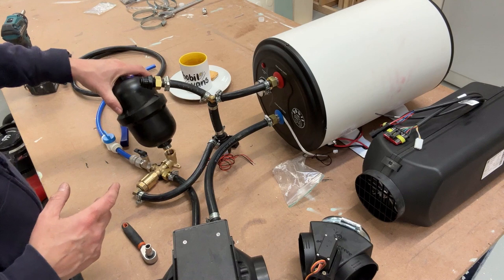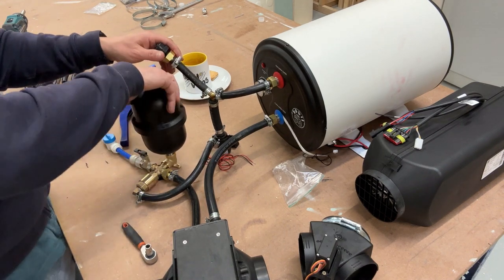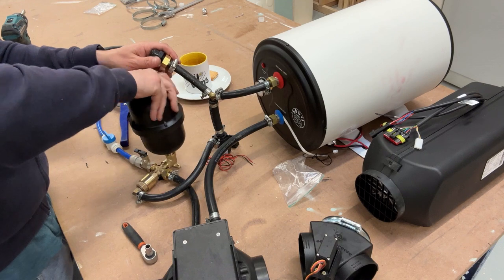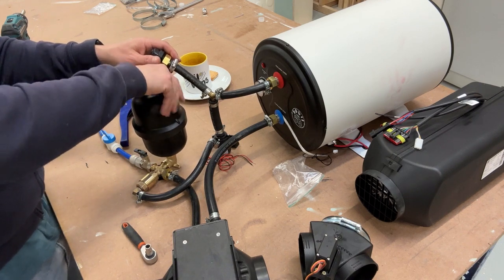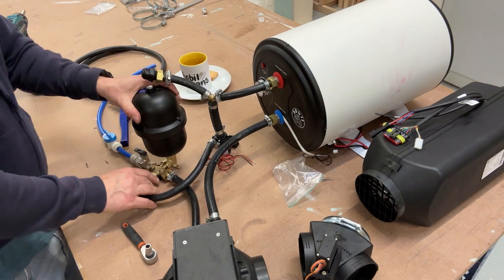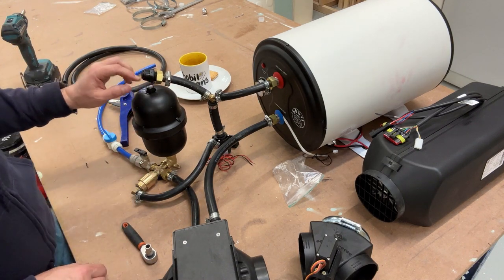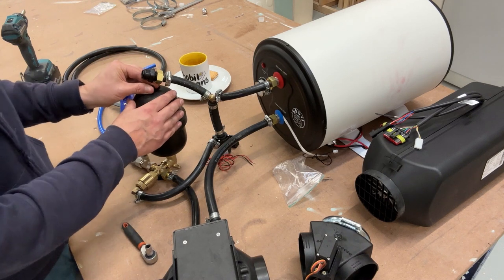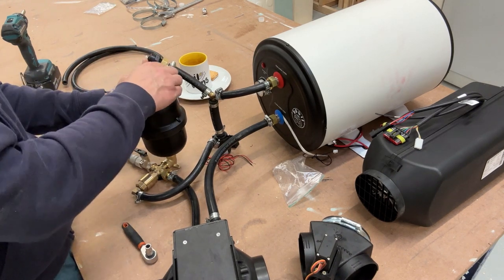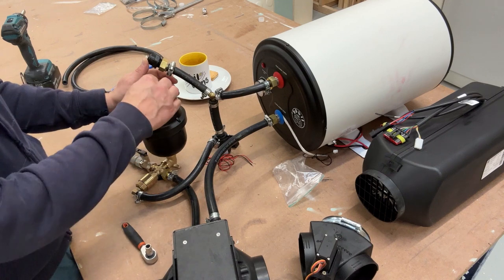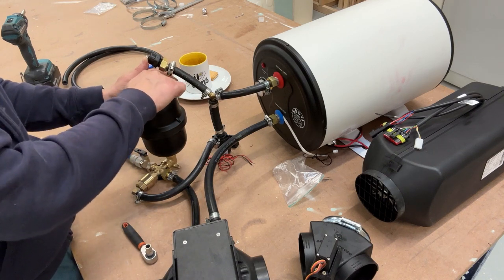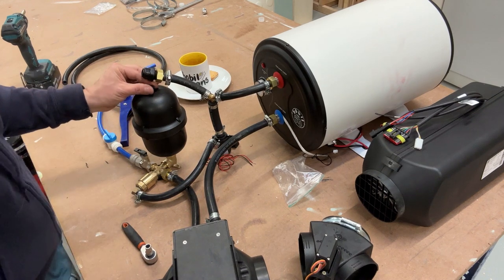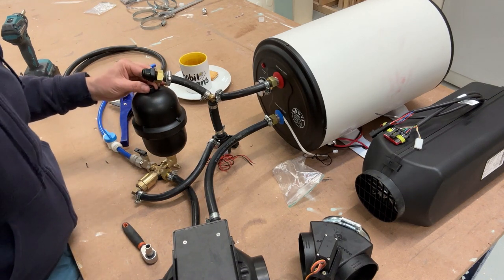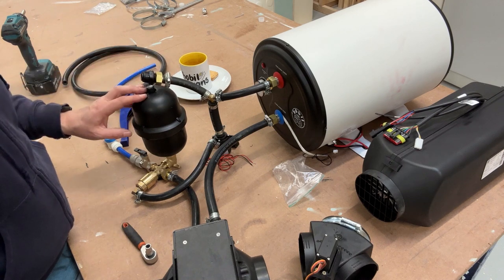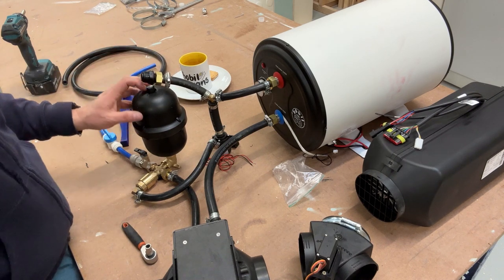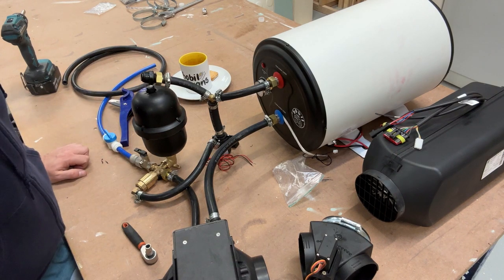That's just a standard thread, and all we do, once this is secured, screw this down. This is set out of the factory for pumps up to 35 psi. If you've got a pump that's higher than that, you will need to pressurize this yourself. It's just a standard bike fitting on the top, so you can connect to that and repressurize that. It generally needs to be about 5 psi higher than your water pump, and you probably want to redo that every couple of years just to make sure that that's still keeping the pressure. And there you go, that is all ready to go.